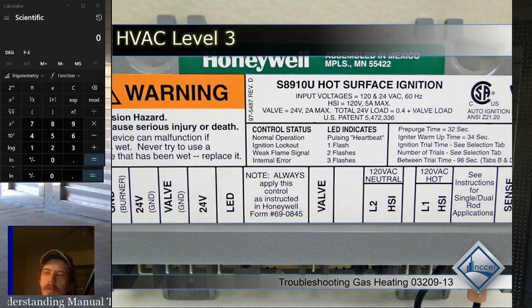Because, if it's below about 45 degrees outside, somewhere around there, the coil is always going to be below freezing, because you have to be colder. The refrigerant coil outside to pick up heat from the outside has to be colder than it is outside, right? If we're going to pick up heat from something, we need to be colder than where we're trying to pick up heat from. So if it's cold outside, the coil is always going to be even colder. So if we just let defrost get controlled by the coil temperature, then the system would stay in defrost forever when it gets, like I said, about below 45 or so.